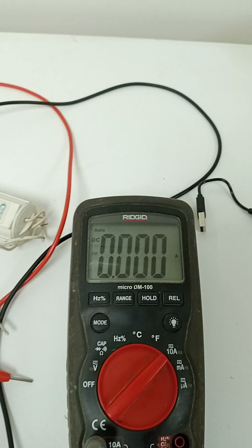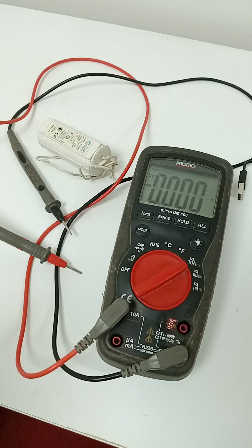Current is always measured in series, not parallel. Voltage is always measured in parallel. Current, meaning ampere, is always measured in series. This probe is always here, the common wire. When you check ampere, this wire connects here, not here. This wire is always here when you check voltage, AC voltage, DC voltage, ohm, resistance, current, frequency, and so on. Thank you everyone.